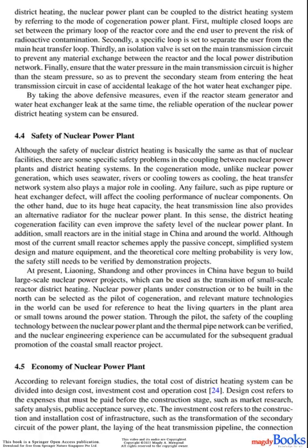Finally, ensure that the water pressure in the main transmission circuit is higher than the steam pressure, so as to prevent the secondary steam from entering the heat transmission circuit in case of accidental leakage of the hot water heat exchanger pipe. By taking the above defensive measures, even if the reactor steam generator and water heat exchanger leak at the same time, the reliable operation of the nuclear power district heating system can be ensured.